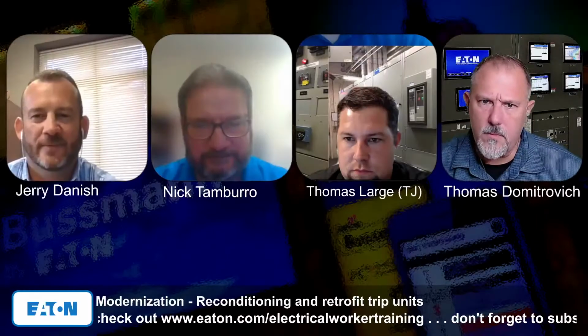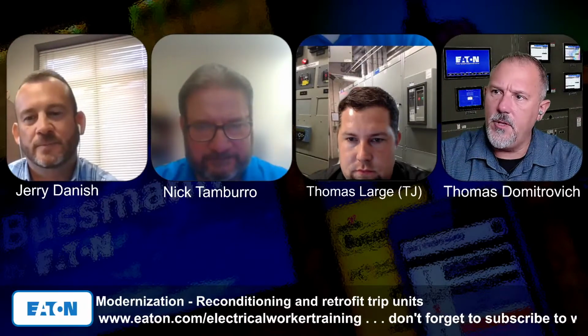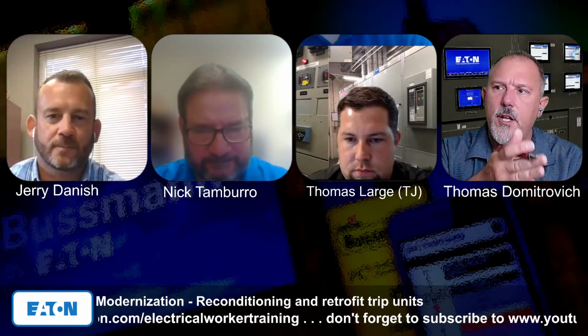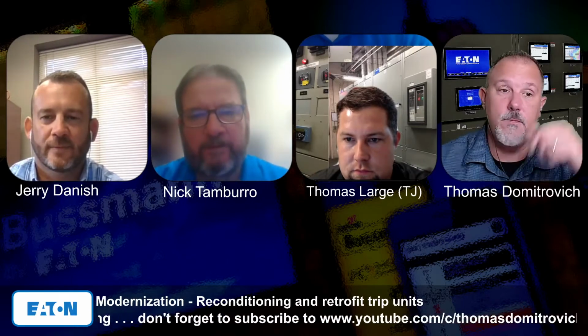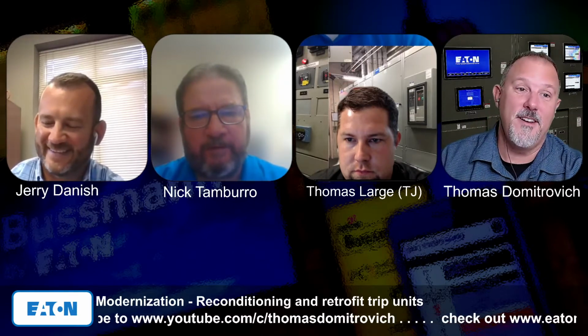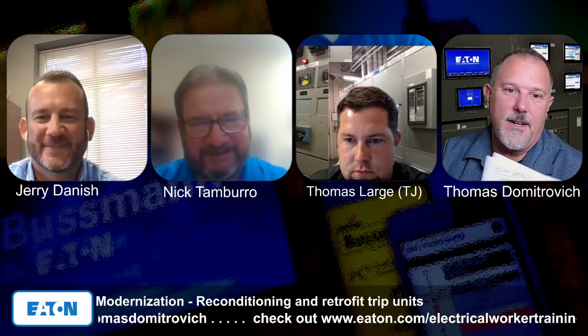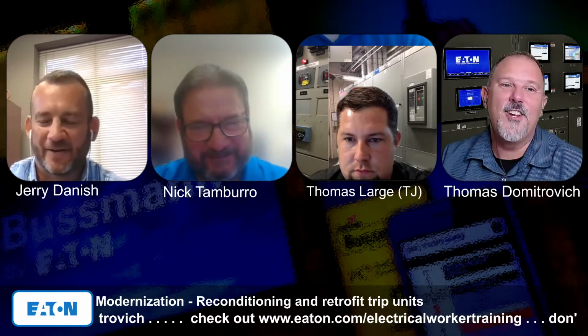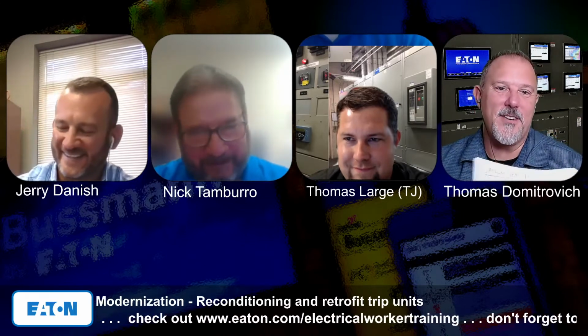So we hit the trip unit upgrades. We talked about class 1, 1G, 2, and 3 reconditioning, the Magnums, the mechanism. And Jerry said we were only going to talk about low voltage power circuit breakers, but you guys had to throw in FAME, factory authorized mechanism enhancement, for medium voltage VCPWs. Man, gotta get it in there. That's what we call a curveball.